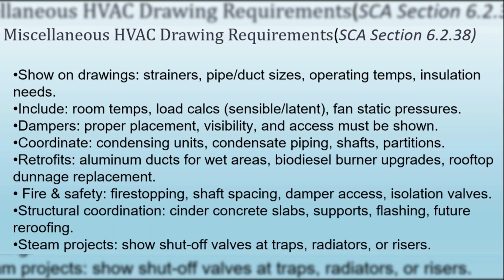This section covers the miscellaneous but critical details that must appear on HVAC drawings for school projects. Designers need to show more than just equipment layouts. For example, strainers must be indicated for coils, pumps, and traps. Insulation requirements must be properly noted depending on temperature differences and condensation risks. And all pipe diameters, duct sizes, and operating temperatures must be clearly documented. Load calculations, room temperature requirements, and sensible versus latent cooling capacities must also appear on the drawings. Designers should show how loads were calculated, ensuring compliance with ASHRAE and NYC codes.